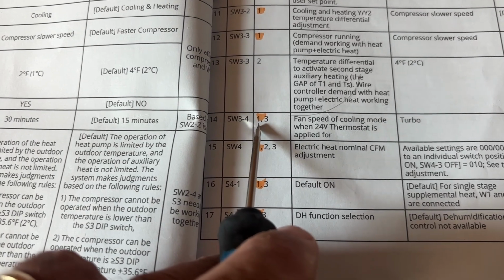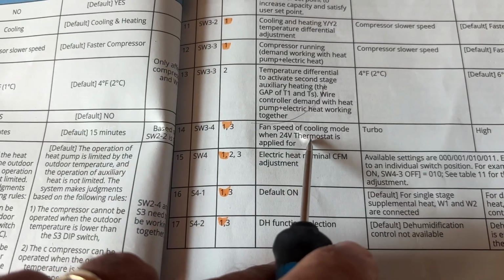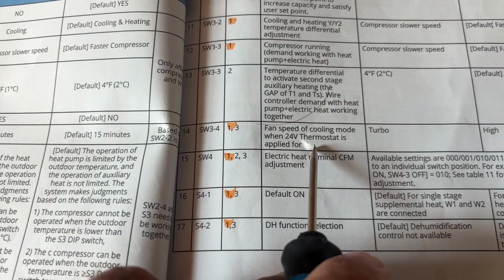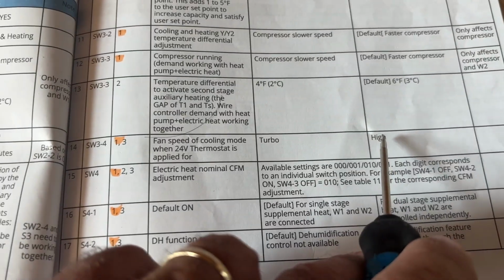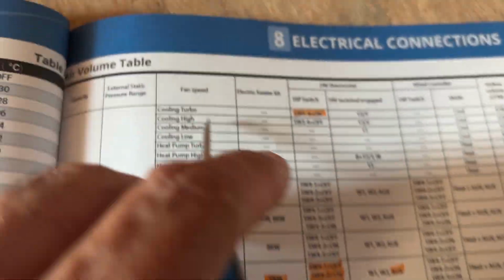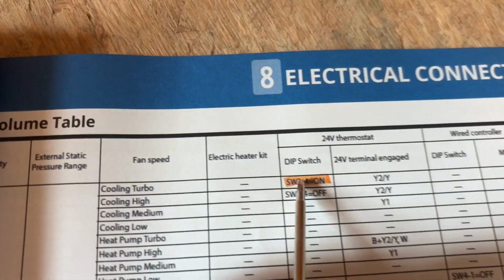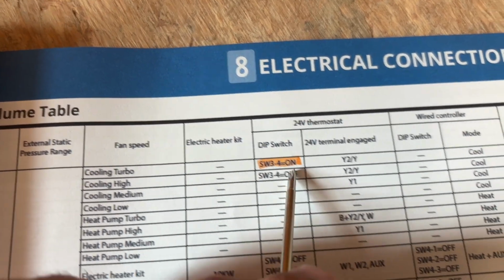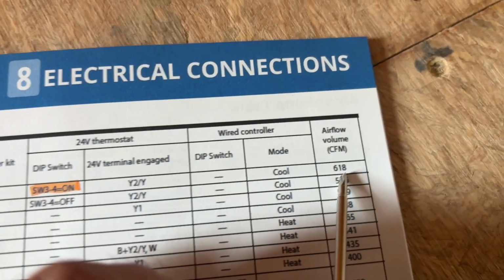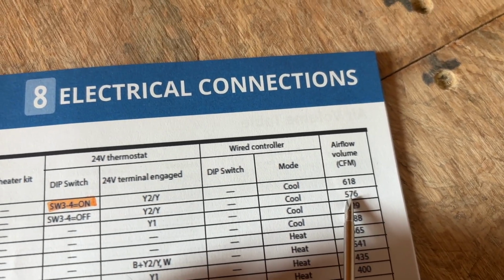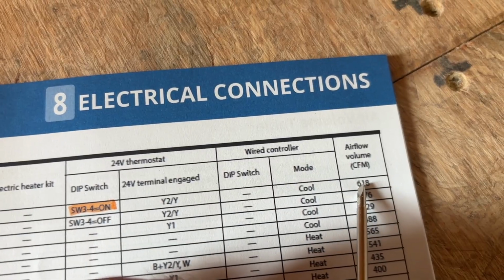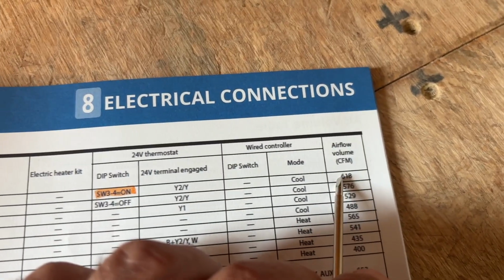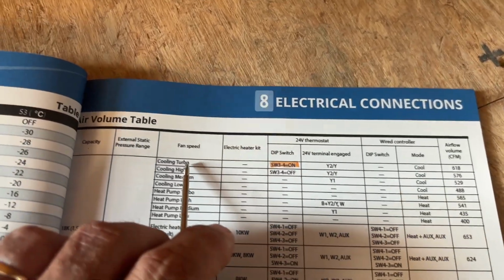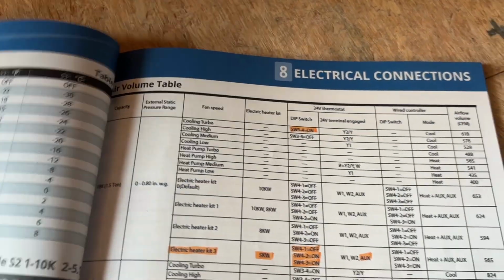SW34, that is fan speed of cooling mode when the 24 volt thermostat is applied for. You have 2 options, high and turbo. And if you go to the back page here, you can see cooling turbo, setting the switch 3, 4 to the on position. My CFM is going to bump up from 576 to 618. So that's going to get me a little more airflow. And with my house and the number of registers, I'm going to set that to on to let the fan run a little bit faster and give me a little more CFM.